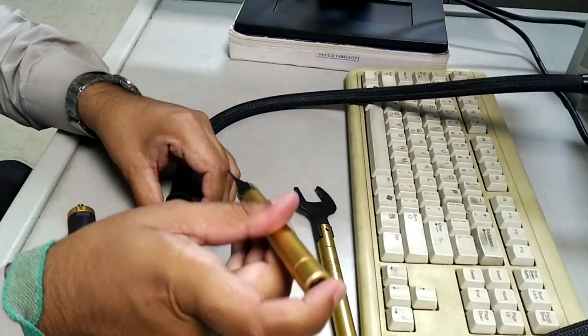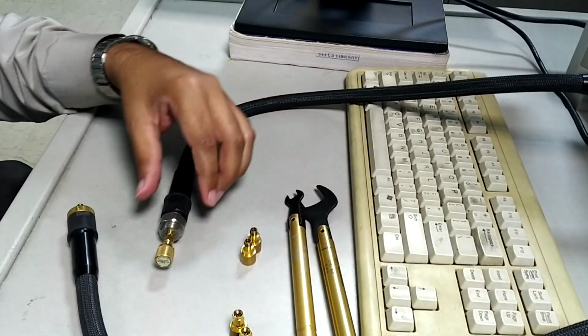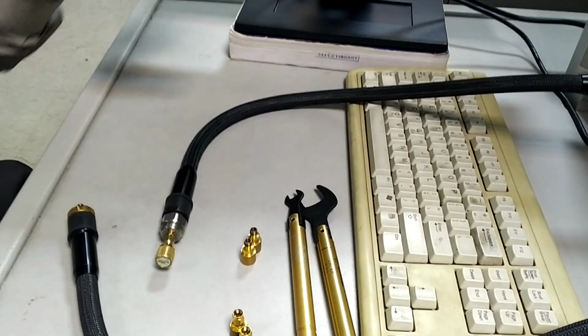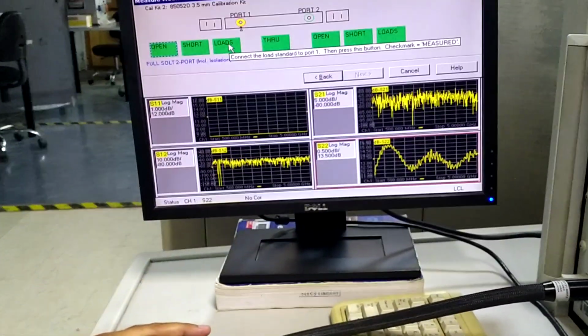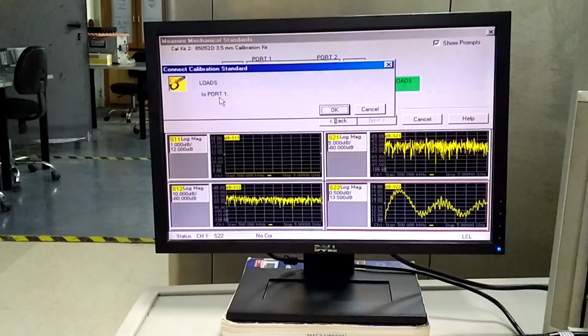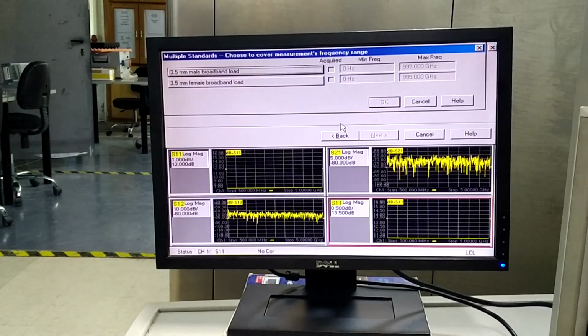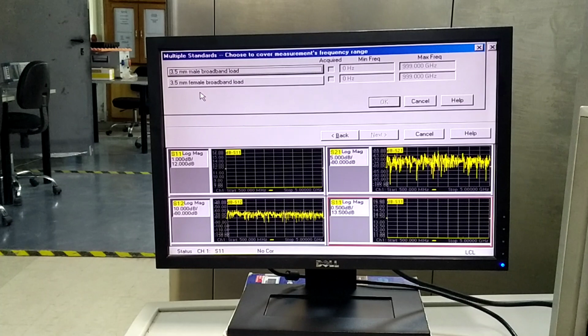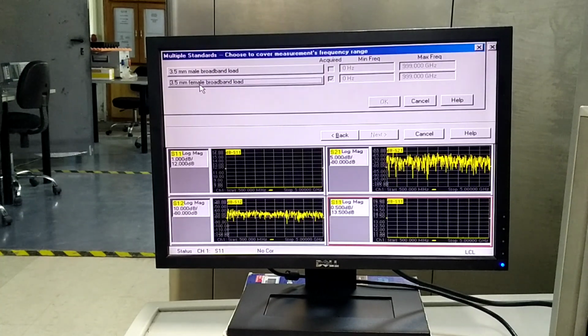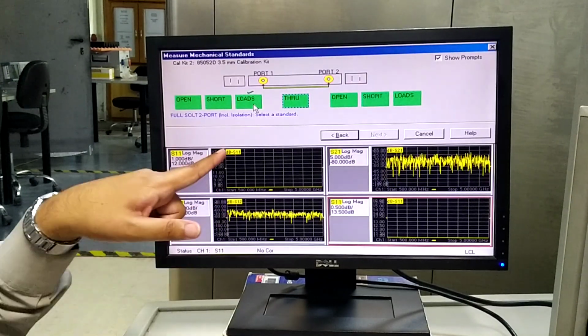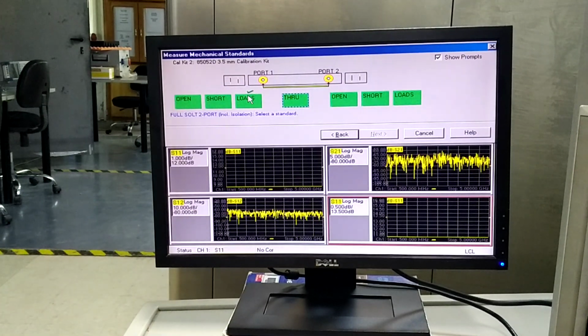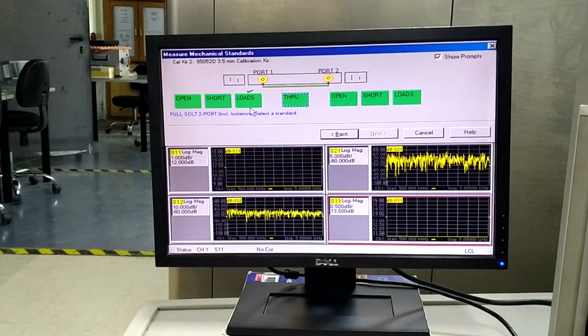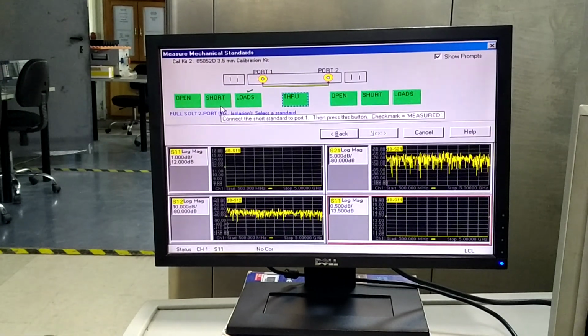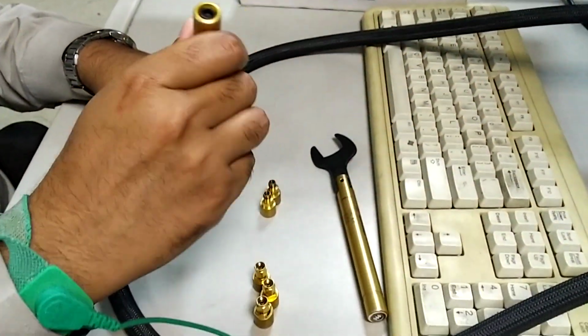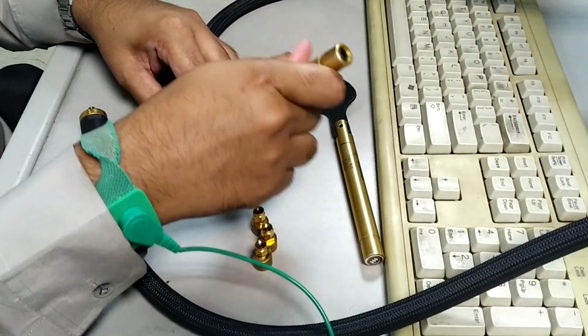So here the connection has been performed, and I connected a load standard here. If you go to the screen now, I click the load here. It says load to port 1. Okay, it's connected. I press OK. Since I'm using a female load, I select 3.5 mm female broadband load. I select this one. I press OK. If you see, there's a green button now, which means that the measurements for the load standard have been saved. Now the next step is to connect the short, and then I connect the open. So let's go to the connection strategy now and connect the short or open standard, whichever is available now.